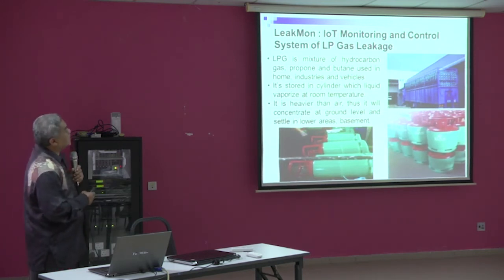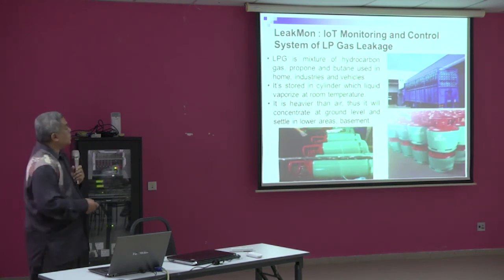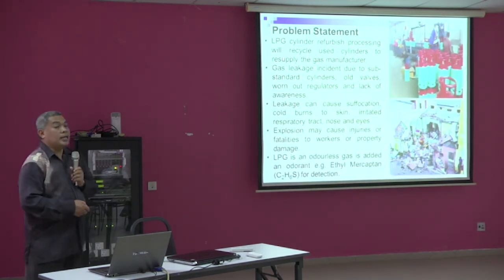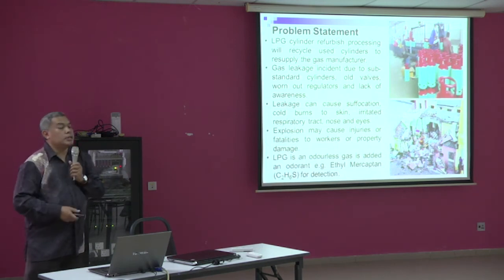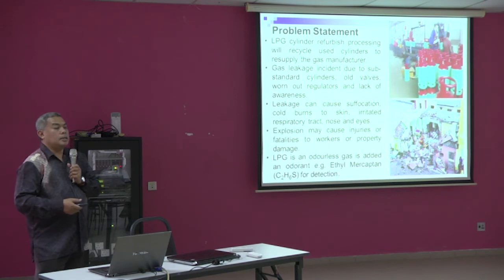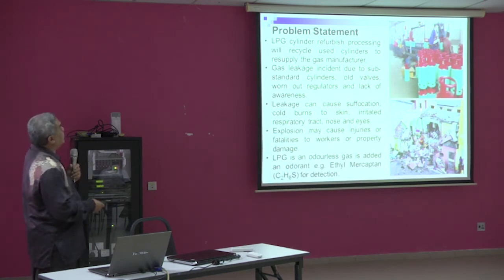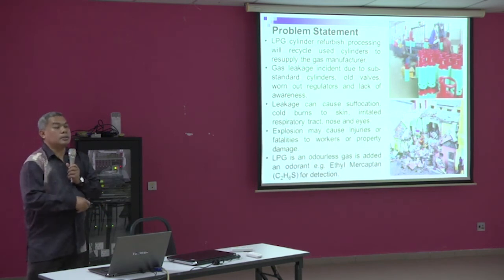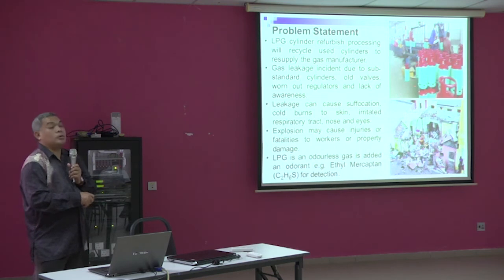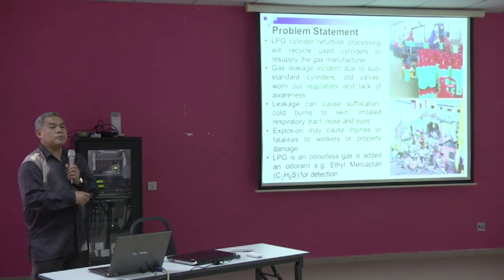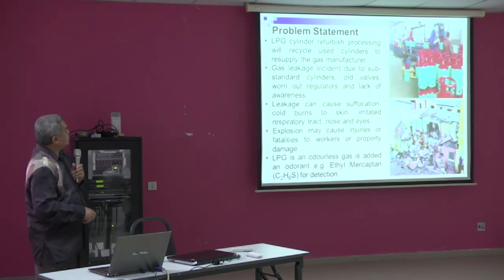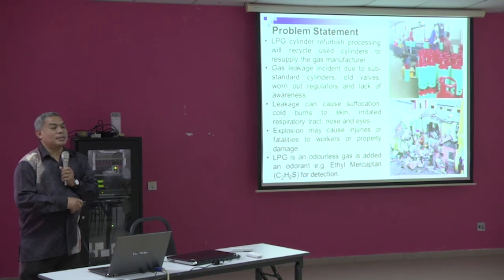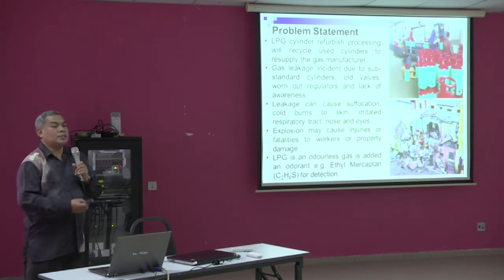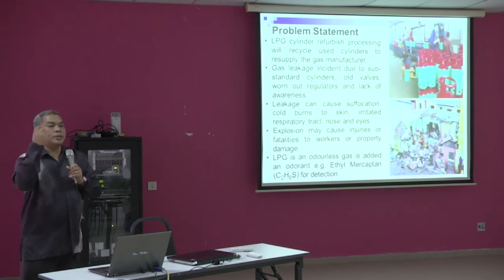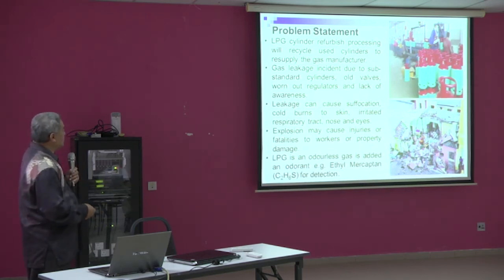Okay, then another application. This is for hazardous gas, LP gas. We are doing this one in Sungai Petani, same concept. To monitor this LPG gas, because LPG gas is quite hazardous. This is a refurbishing company. That means the whole tank, whole cylinder, after some time we have to go back to the factory to refurbish, to check the valve, to check the connection, etc. So what happens? The workers over there, normally the tank is not completely empty. They just pull it again, and it bursts in the air. So it's quite dangerous.